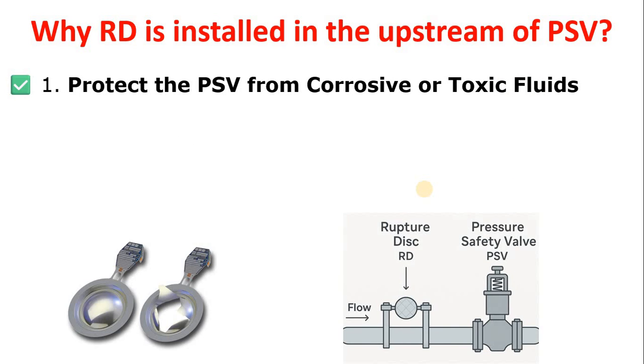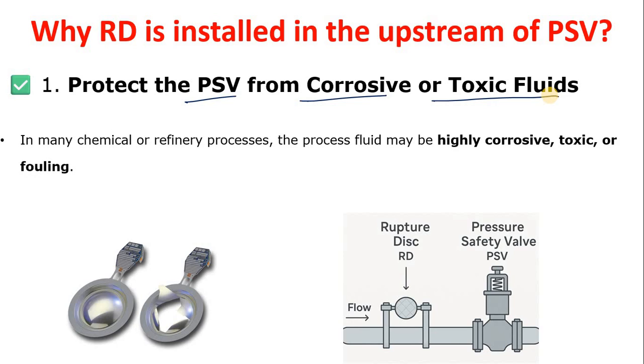The first reason we use a rupture disk upstream of a PSV is to protect the PSV from corrosive or toxic fluids. If you are handling a corrosive process fluid — such as hydrogen sulfide, hydrochloric acid, ethylene dichloride, or amine — and you are not using a rupture disk, the process fluid will directly contact the PSV's internal parts, including the seat and disk.